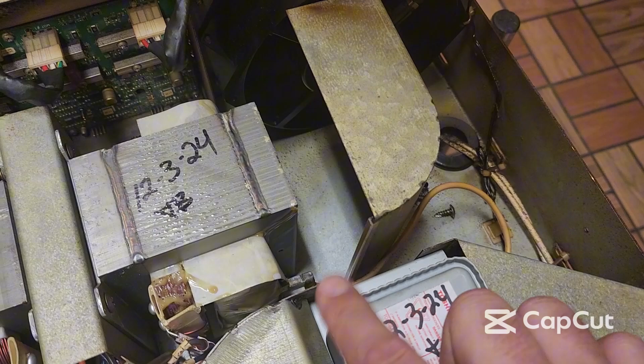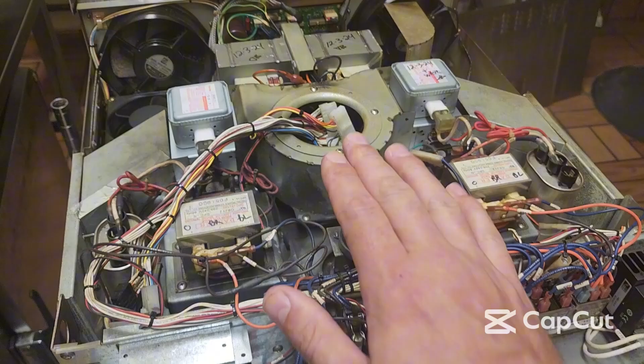A lot of this can actually be tested without voltage, so we'll go over how to test these using your ohm setting on your multimeter in a bit. Basically, if you're not getting volts back there or something's not working quite right, you can start checking your relays to see if you're getting voltage, or check those points coming off of the board themselves.